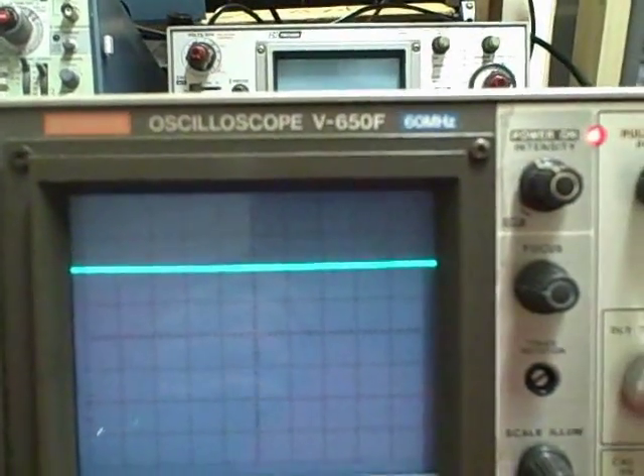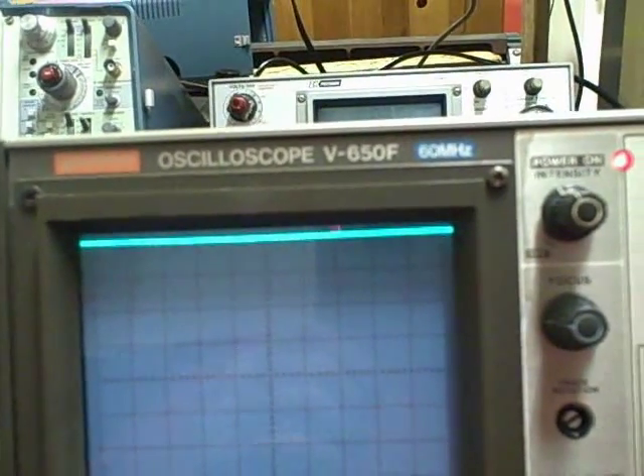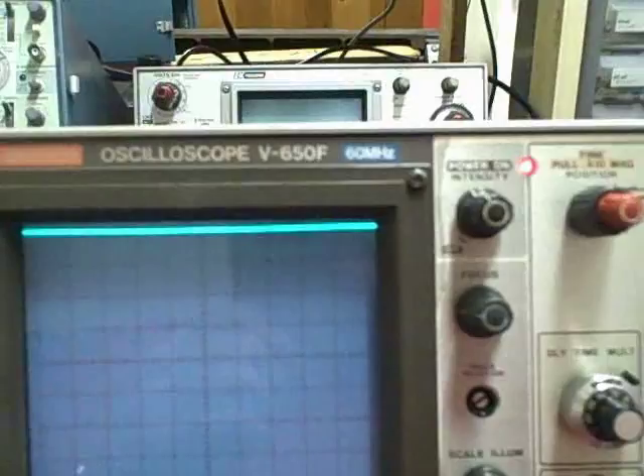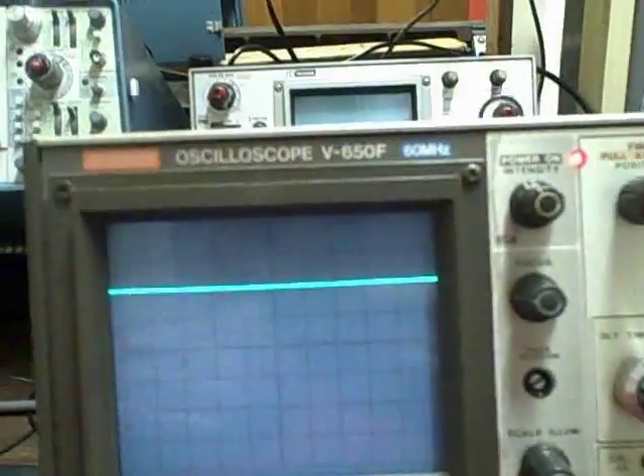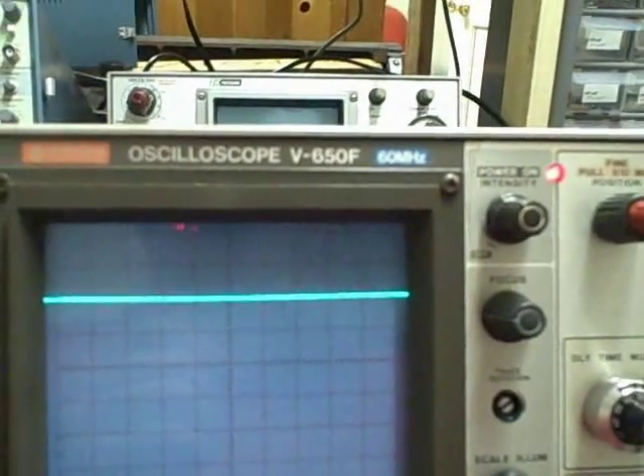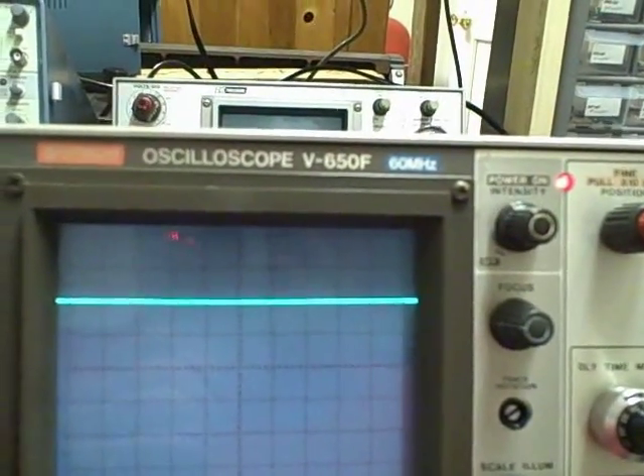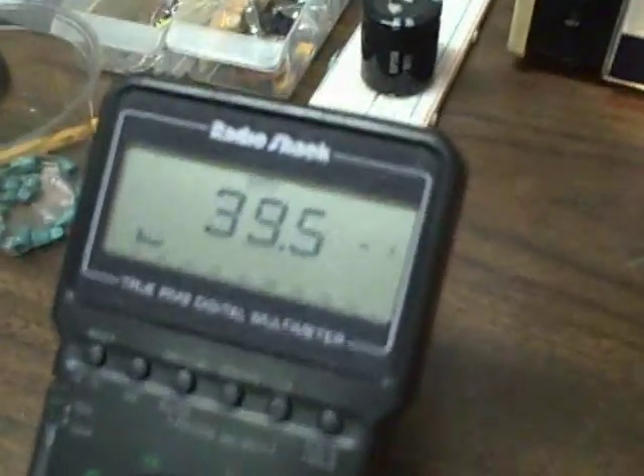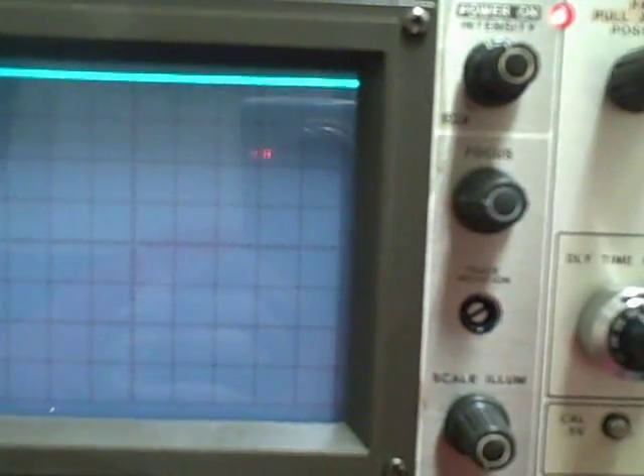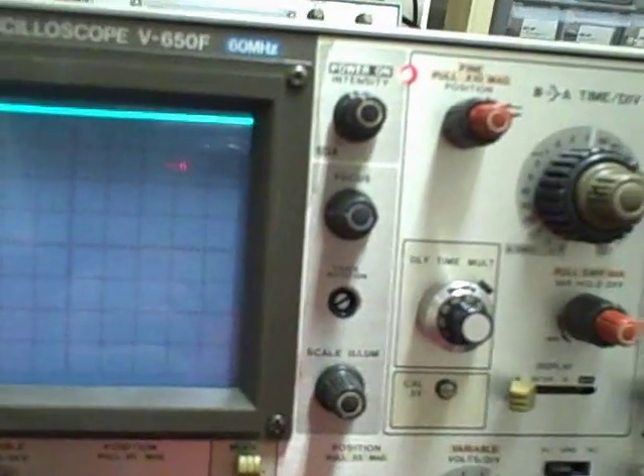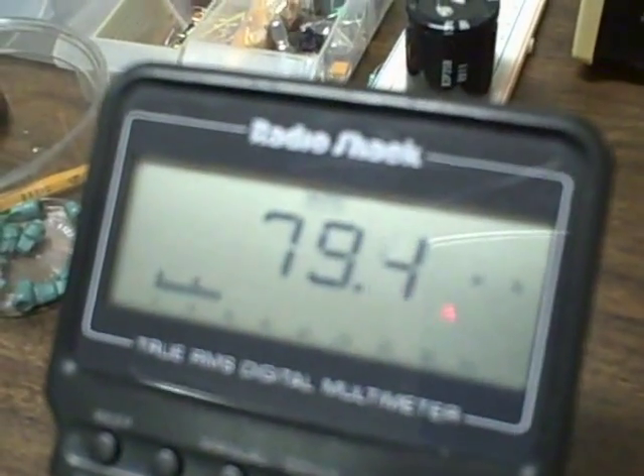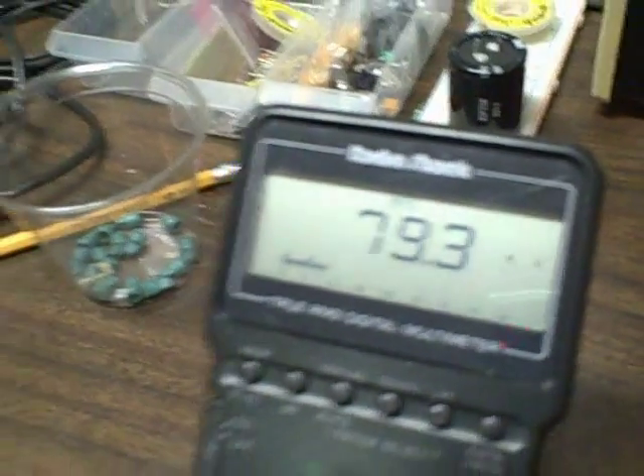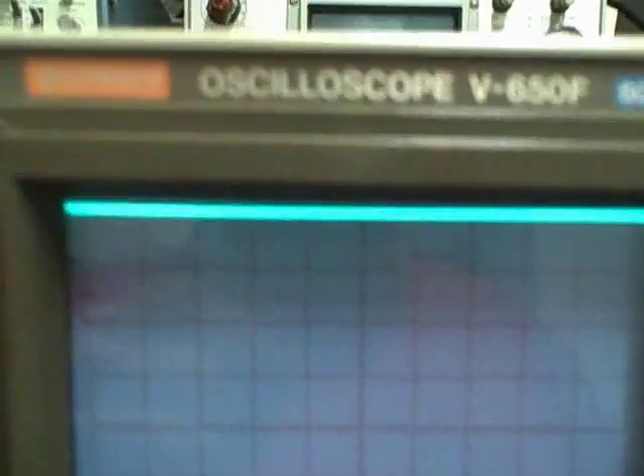Let's go ahead and kick this up to full scale. And then I should be able to see that I am now at 40 millivolts, which I am running 39.5, so we are right there. Let's go ahead and drop to 20 millivolts per division. We are riding at division two, which at 20 millivolts per division, that would be 40 millivolts. And we are still at 40 millivolts. So let's go ahead and kick that up full range. And I should now see 20 millivolts per division times four is 80 millivolts. And I should be reading 80 millivolts over here. And I'm running 79.3, which that's because I eyeballed it when I adjusted it. But hey, that's perfect.